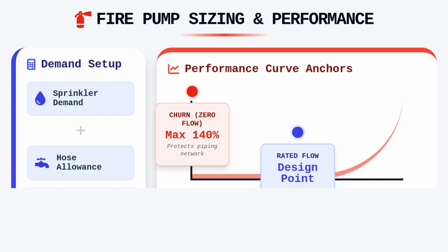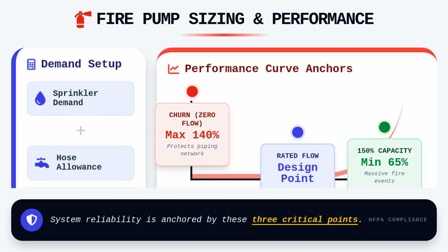At the churn point, the pump must not exceed 140% of the rated pressure, a constraint that exists to protect the downstream piping network from overpressurization during low-demand events. Conversely, at 150% flow, the pump must be capable of delivering at least 65% of its rated pressure to ensure that high-velocity fire suppression requirements are met during an actual, massive fire event. These 3 points, churn, rated flow, and 150% flow, are the anchors of pump selection and verification.